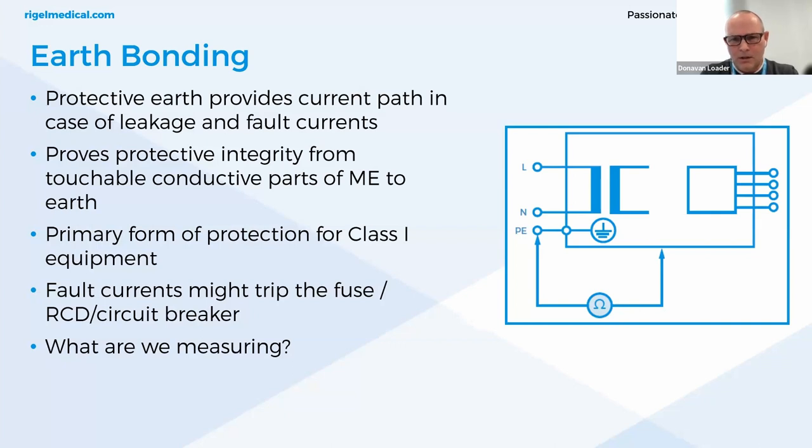For earth bonding, protective earth provides a leakage current path in case of fault currents. Several types of class 1 medical equipment have multiple exposed conductive connections, such as patient beds and sterilization baths. It provides protective integrity from touchable conductive parts of the medical equipment to earth. Routine testing of earth bonding is crucial to ensure an adequate connection between the conductors and the mains plug. Over relatively short periods of time, connections or bonds can fail, leading to an increase in contact resistance, particularly in high workload, high-stress medical environments.